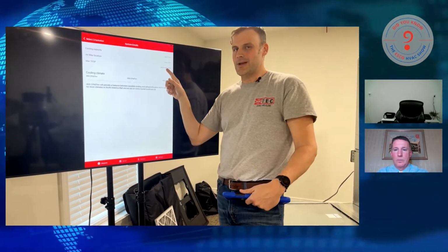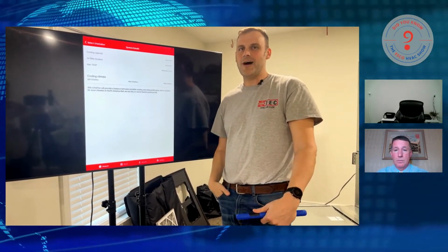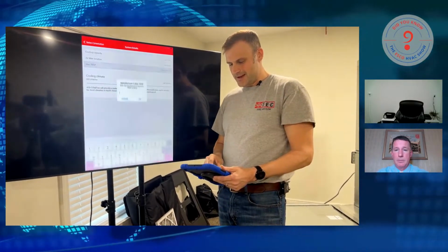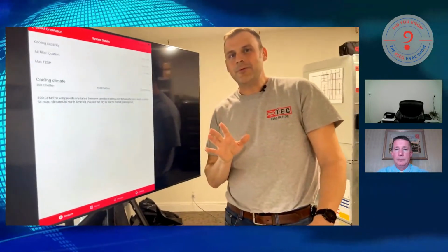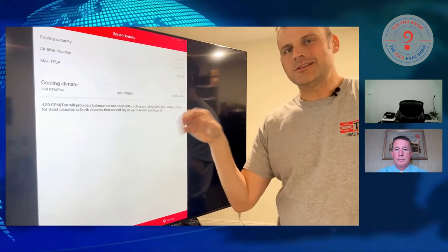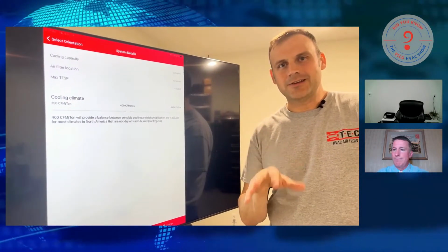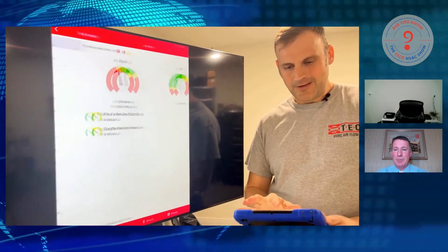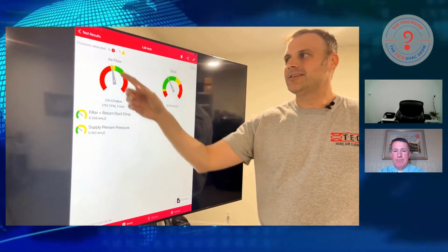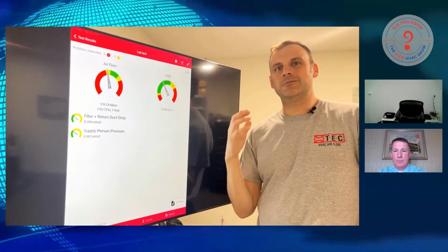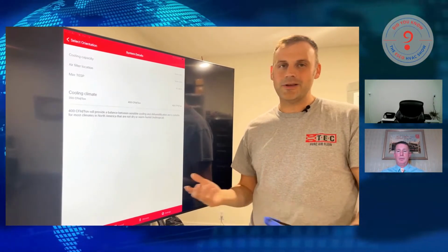It's default to 0.8. Let's say you've got a furnace, you go look up the literature, and the literature on the furnace says it's 0.5 maximum TESP. You're going to touch that, enter 0.5, and click OK. And there you go. Now, what's going to happen with that? When you make that switch in the settings in the back, when you get to measuring and all the dials come into play on that technician-friendly screen, this screen here, all of these dials are going to adjust for you. All of these settings will be changed based on the new TESP that you have dictated in the app. So that's a new feature that's about to drop, along with heat mode.